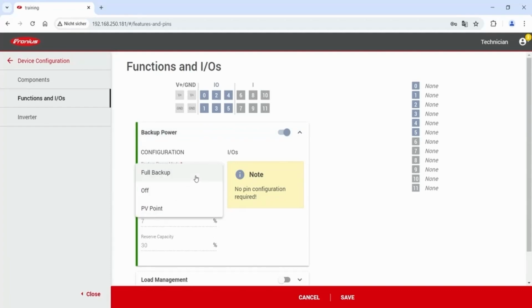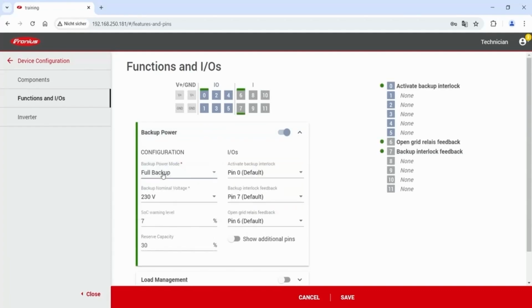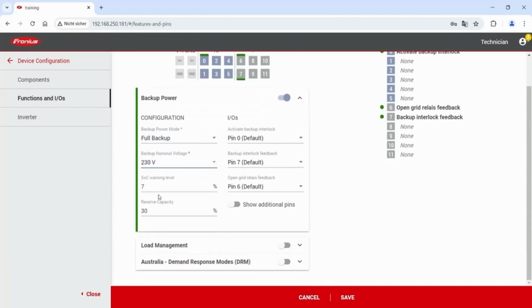First of all, we are switching to, in our case, full backup functionality, and then we can set a backup power nominal voltage, in our case for example 230 volts, as well as the SOC warning level, and the reserve capacity can be set in this mask. On the right hand side we have our digital IOs, and please note we always recommend you to use the default settings, so pin 0, pin 7 and pin 6 for the activation of backup interlock, for the backup interlock feedback, as well as for the open grid relay feedback. Since these are the numbers that are also written down on the backup controller, it's always the easiest choice to stay with the default values.